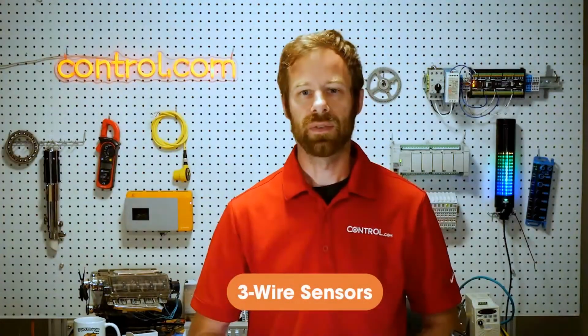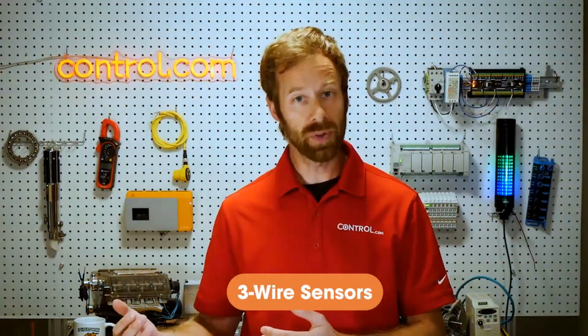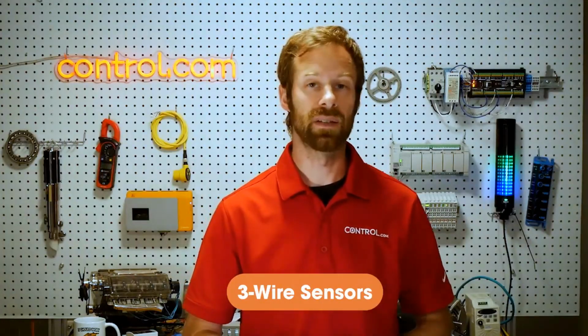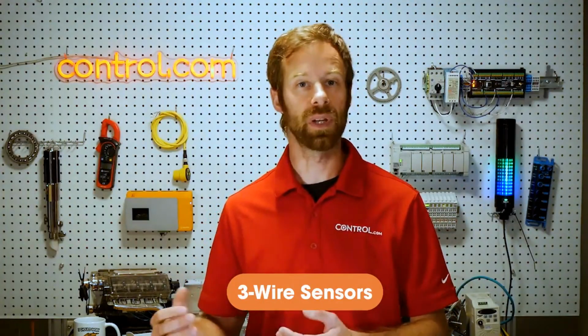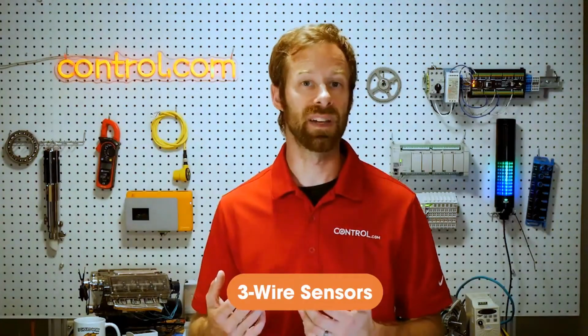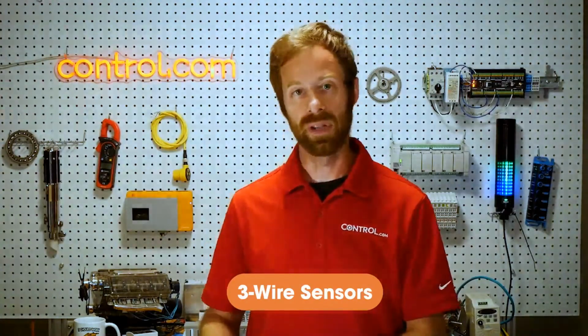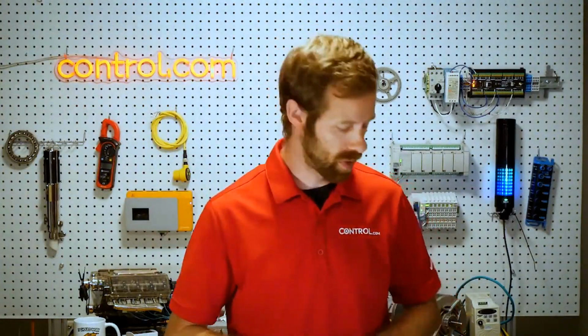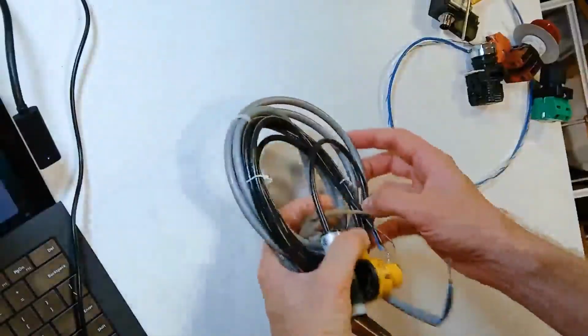The next category of switches that we're going to look at are 3-wire sensors. They still provide single direction data flow. That is, the electricity only flows between the sensor and the controller. It's meant to convey a signal, not any further information to the sensor, but they're a little bit more complex in the way they operate as compared to the switches. So here's a few examples.